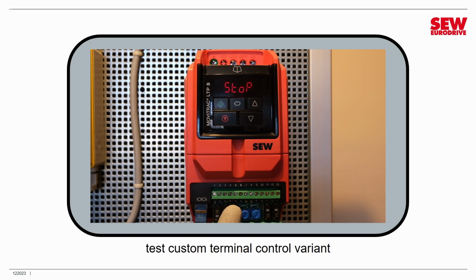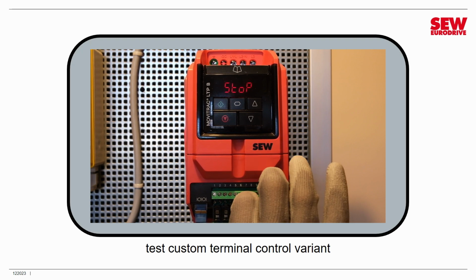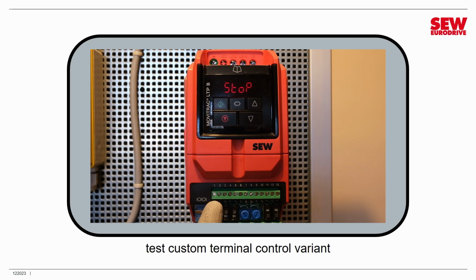We're going to test out the ramps now. So we're switching back to potentiometer control mode. I'm going to turn it all the way up, so we'll go at our top speed, 1800 RPM. Now let's decelerate. We're on our normal ramp because digital input 5 is off. You can see that did take some time.